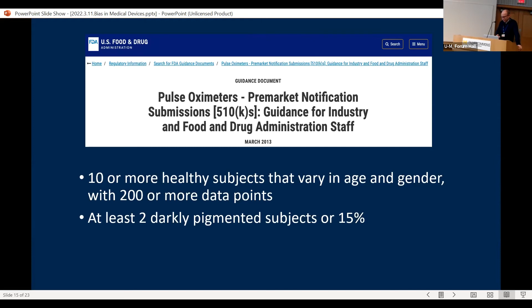And to do that, you need to show data of 10 or more healthy subjects that vary in age or gender and 200 or more data points. And at least 2 darkly pigmented patients, or 15%, should be in your sample. And that right now is the extent of the FDA's regulation of pulse oximeters. And anyone with any sort of knowledge of data would appreciate the fact that having 2 darkly pigmented subjects in your sample is not going to be enough to really be able to discern whether there's actual real bias in the pulse oximeter based on things like your skin tone.